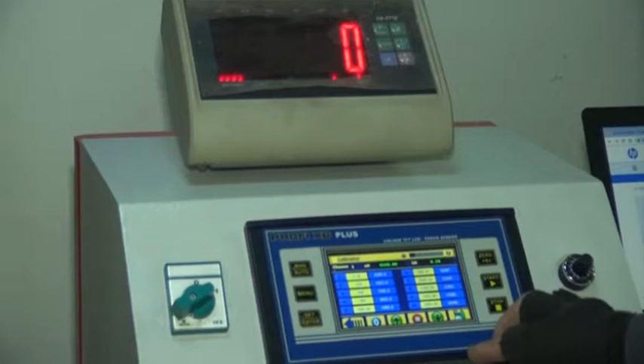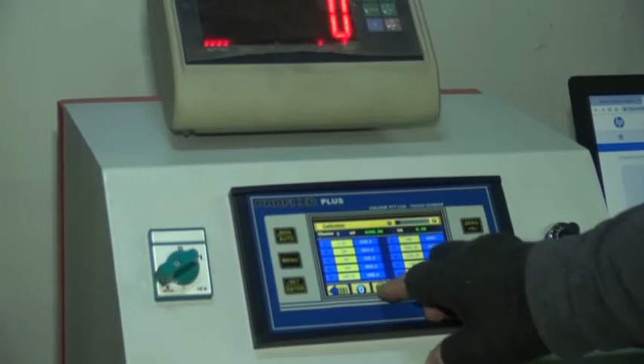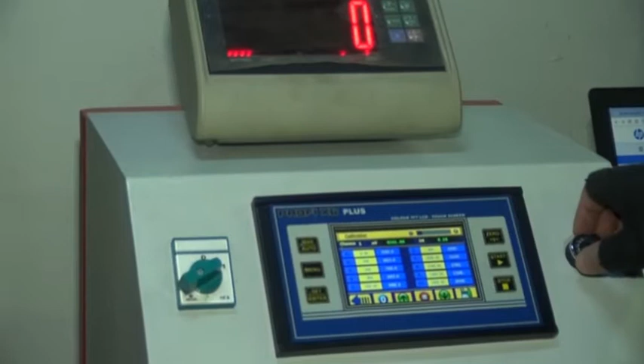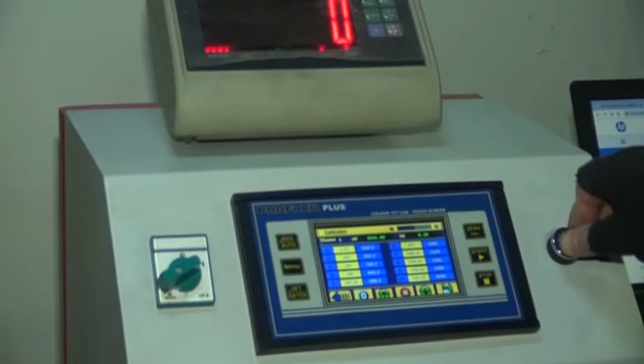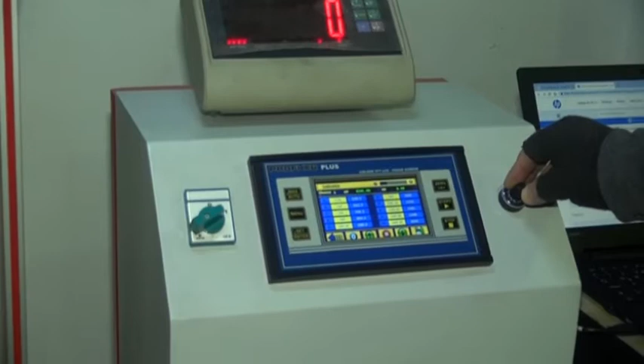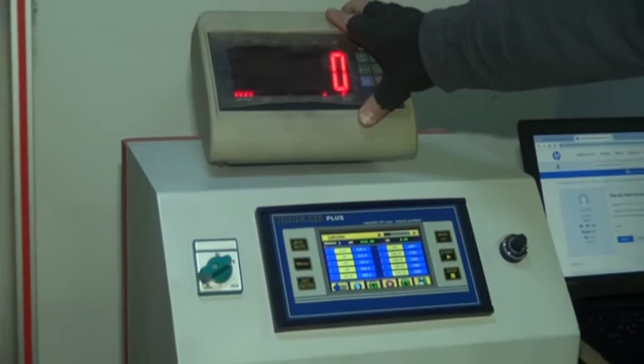Whichever steps I want to follow, I'm going to enter all the necessary steps. For example, if I want to make only 4 steps, I'm going to enter 0 for the 5th step. That means the software calculates the calibration value only based on the first 4 numbers, and the rest of the numbers will not be taken into consideration in that condition. So I go back, and then I'm going to start the machine by pressing the arrow key, and the machine starts. And then I can adjust the loading speed by using the calibration potentiometer. This is higher speed and lower speed. Also, I'm going to follow the reference load on the calibration display.